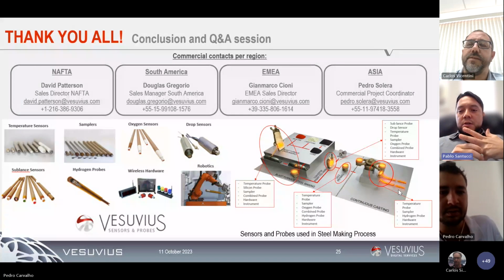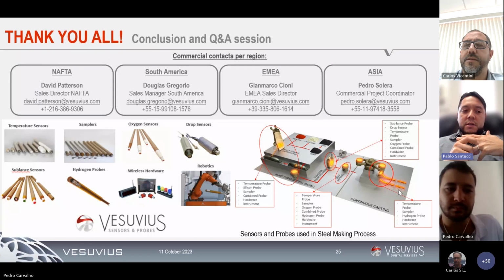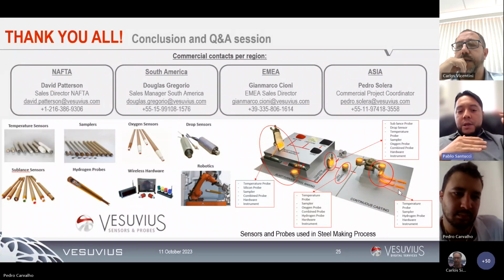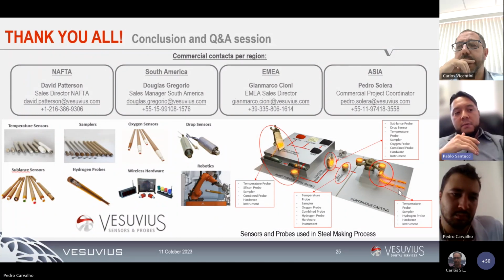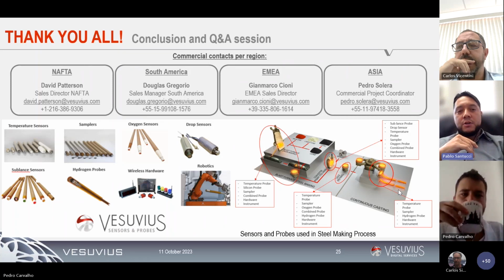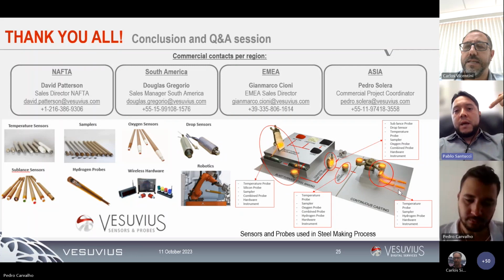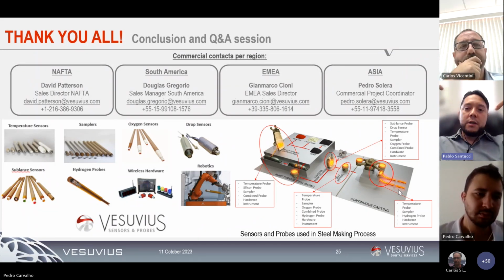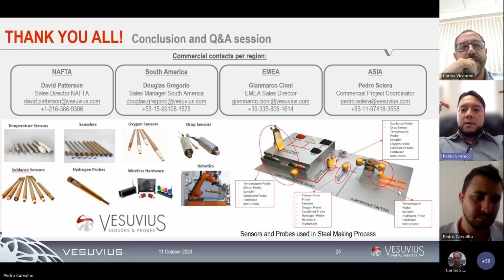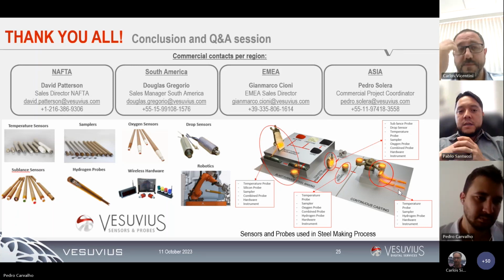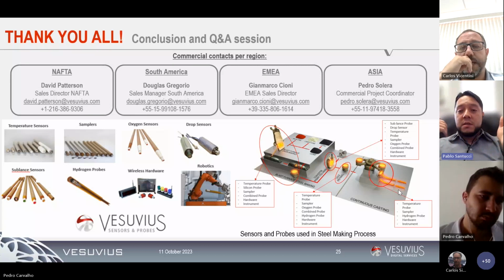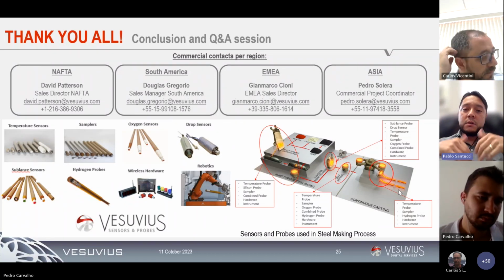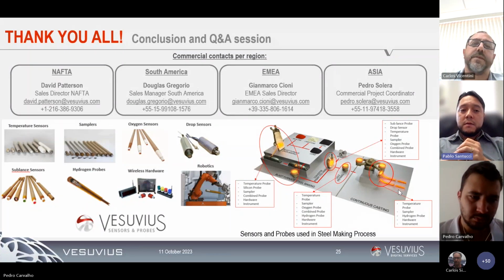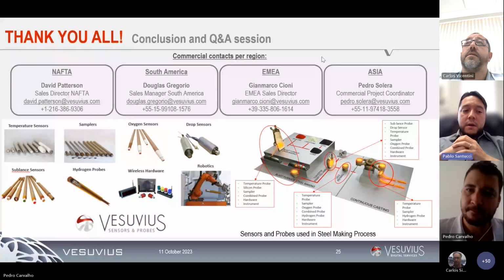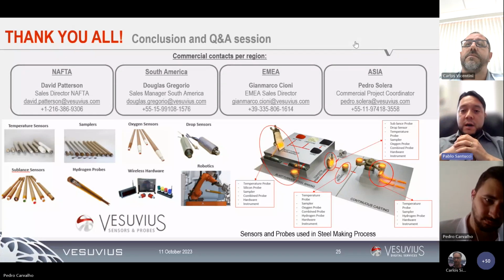Yeah, the answer could be yes, Roberto, depending on how frequently you have been getting those ppm differences. Let's say you are monitoring the hydrogen back to back, and you take one reading from a hydrogen system connected directly to the nitrogen line from the plant, and another one from the bottle. If you take these comparisons back to back over an extensive time, and the difference still persists, I would say it's possibly a contamination in the nitrogen line from the plant, because the nitrogen tank is already certified and comes with a high level of purity.